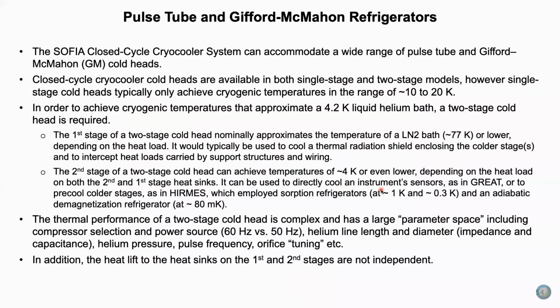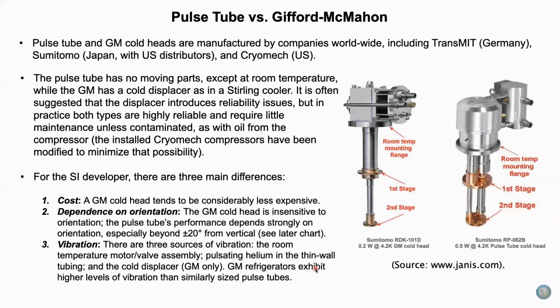The second stage of the two-stage cold head can achieve temperatures of 4 Kelvin or even lower, again, depending on the heat loads. And it can be used to directly cool an instrument's sensors, as in the GREAT SIs, or to pre-cool colder stages, as in HIRMES, which employed sorption refrigerators and an ADR. Thermal performance of a two-stage cold head is complex and has a large parameter space, so a lot of things can affect its ultimate performance. The heat lifts to the heat sinks on the first and second stages are not independent. So if you put heat on the second stage, that'll affect the temperature of the first stage as well.